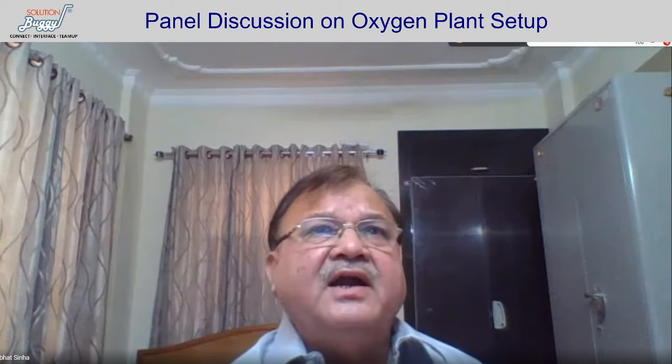And you will get a break-even in a period of only 18 months if you go for a PSA plant that may be costing around 1 crore or something like that, depending upon the size. And that way, very easily you can get the break-even with a PSA plant if it is set up in the hospitals. But buying cylinders, that is very costly. Industrial cylinders or medical cylinders, that is very costly.